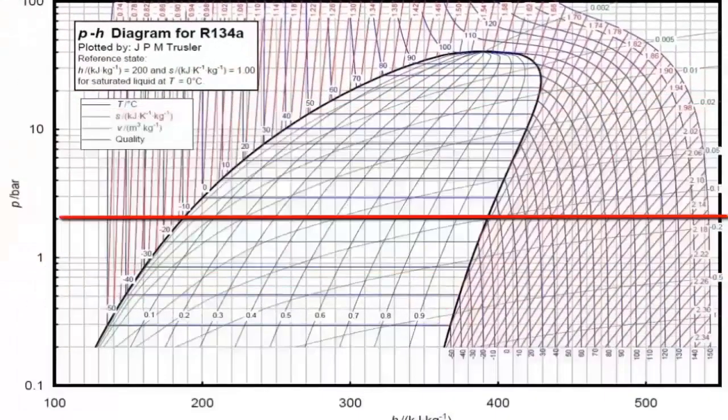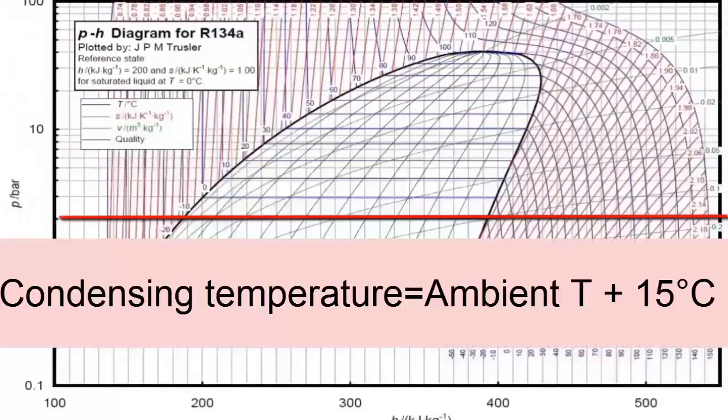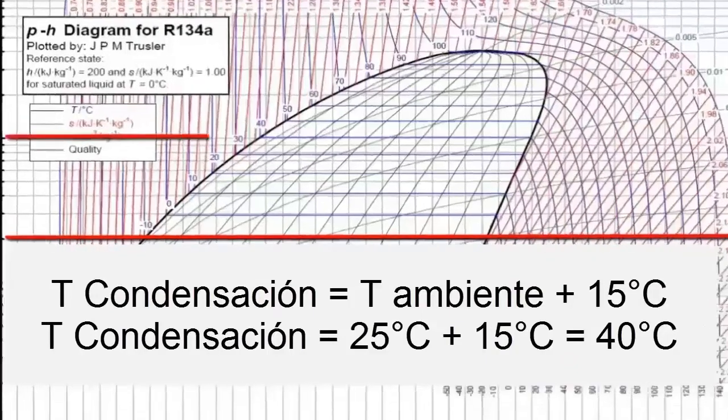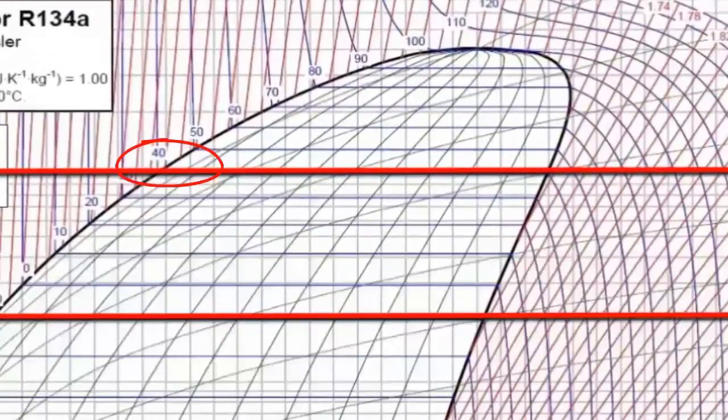Now to find the condenser pressure of the system, it is required to know the temperature of the outside environment and add 15 degrees to this value. For example, for an external environment temperature of 25 degrees Celsius, adding the 15 degrees mentioned, there is a condensation temperature of 40 degrees.